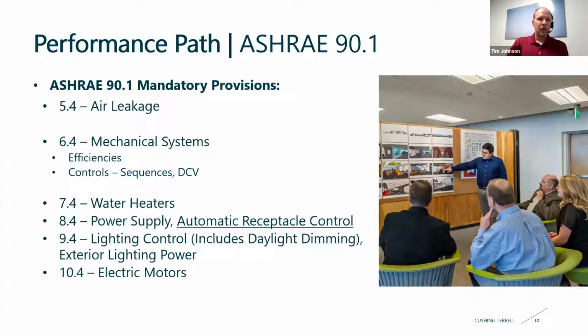All right, moving into 90.1, which is the first one we see from IECC. The mandatory provisions are air leakage. There's a couple of ways to do that. You can test the whole building, or you can do it by material and assembly. Mechanical systems, there are certain efficiencies that we have to work in there. Lots of tables for that. And then on the control side, there's certain sequences that we actually have to provide for various systems.